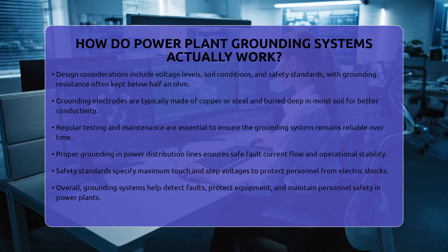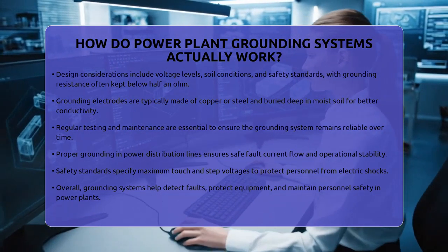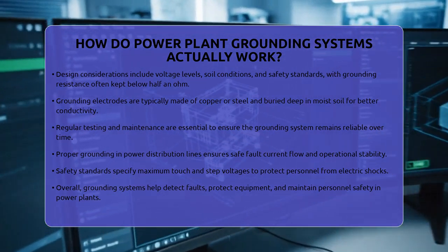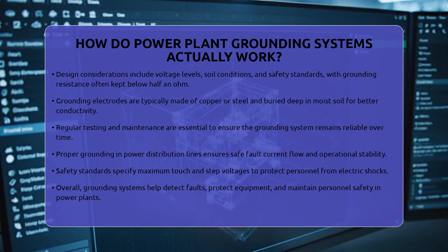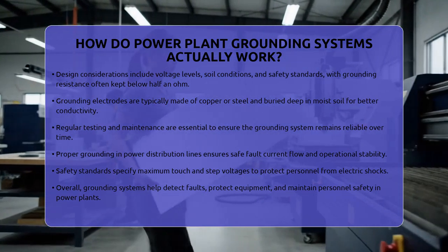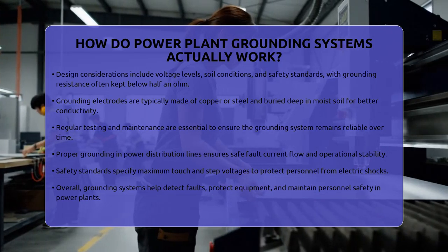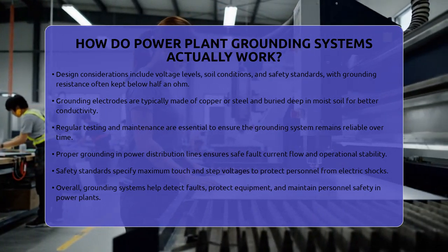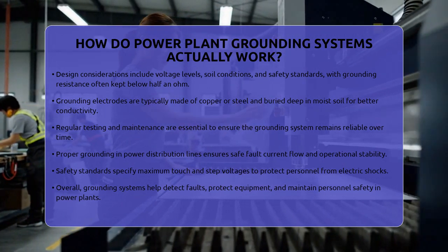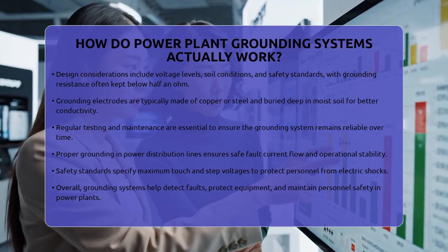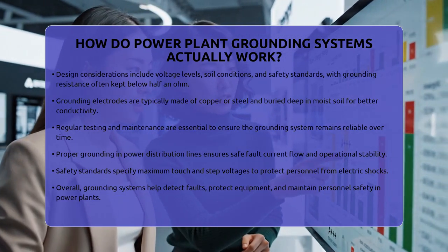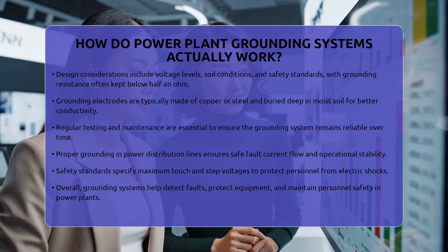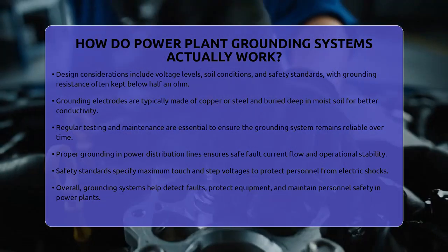In power distribution, especially where underground cables meet overhead lines or enter substations, proper grounding ensures safe fault current flow and smooth operation. Standards set by national and international agencies specify maximum touch and step voltages to protect people from electric shocks. Following these rules is essential for safety and legal compliance.